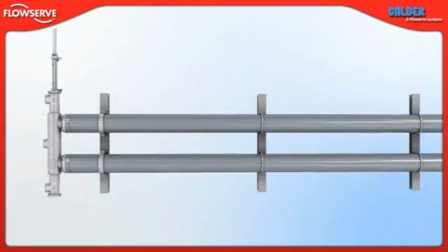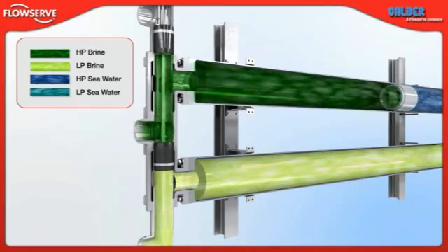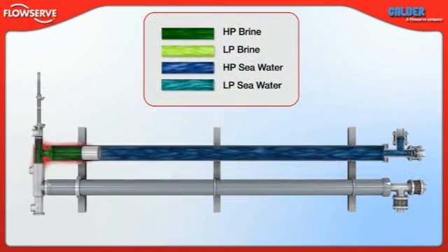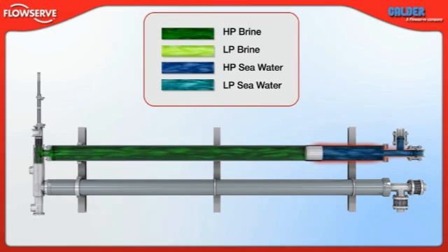Now let's look at the process in motion. High pressure brine from the membranes enters the LinX valve and is directed by its piston into vessel one, which is already filled with low pressure sea water. In the vessel, the pressure of the brine is transferred to the sea water, which then exits the DWEER through a check valve.